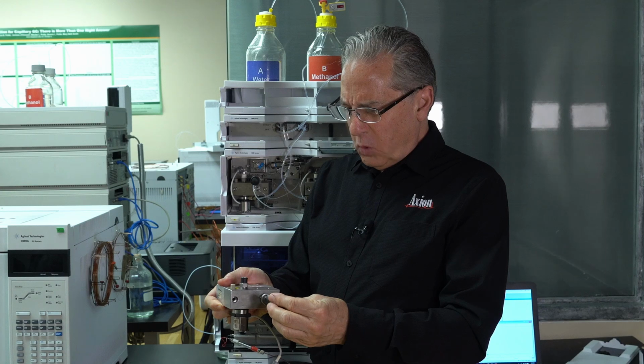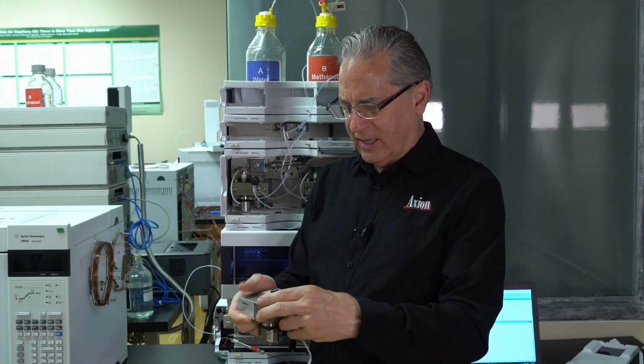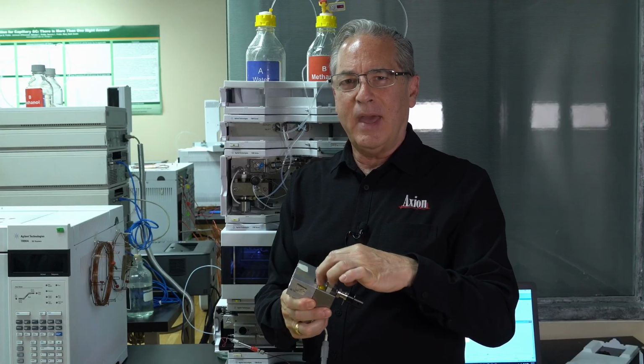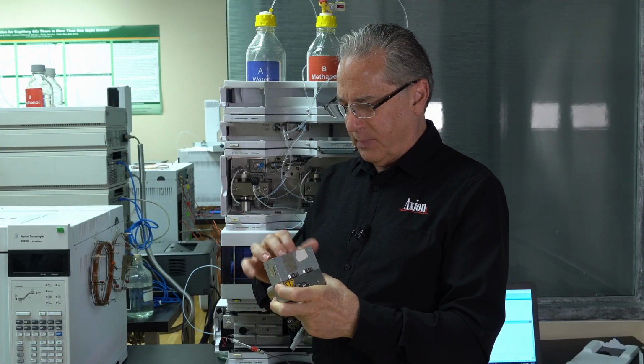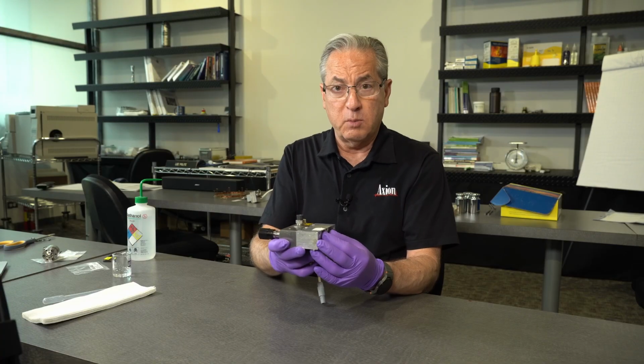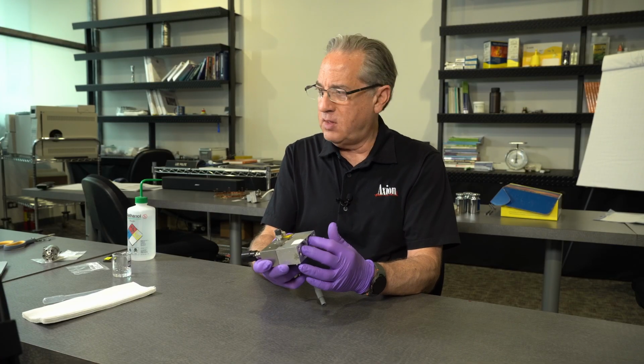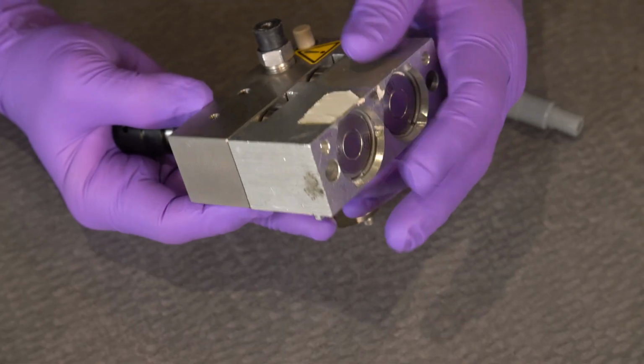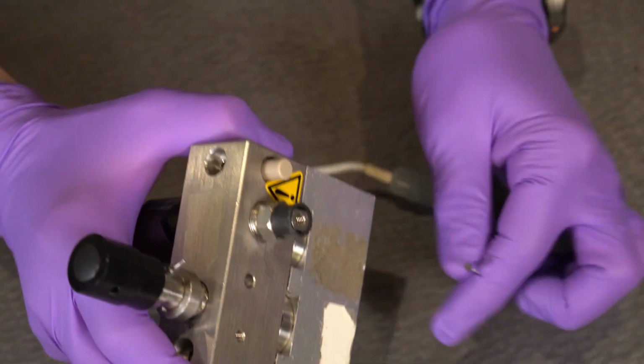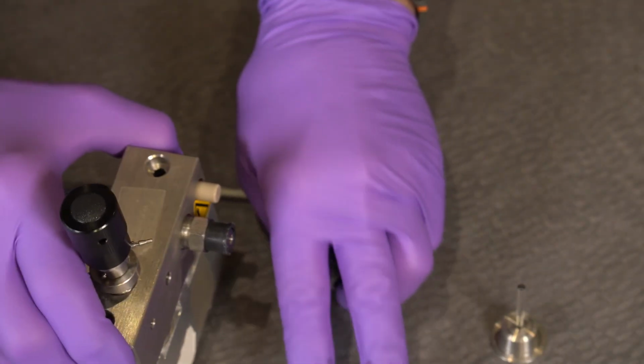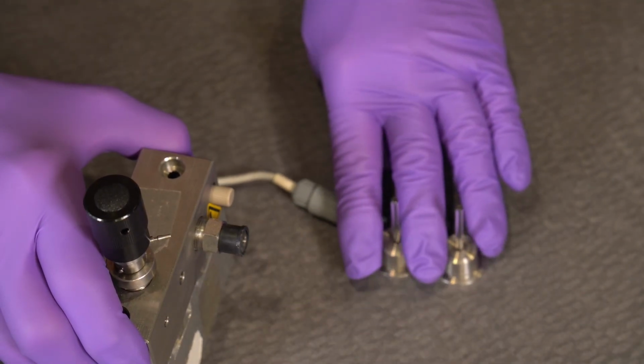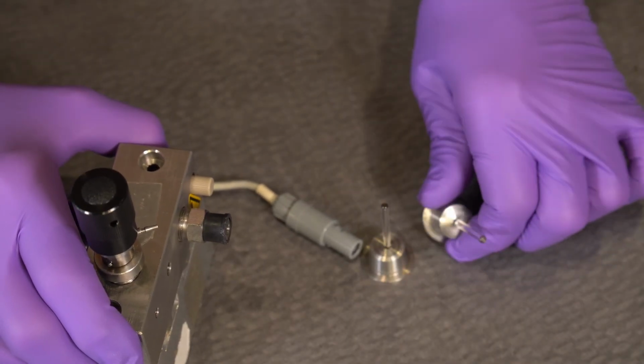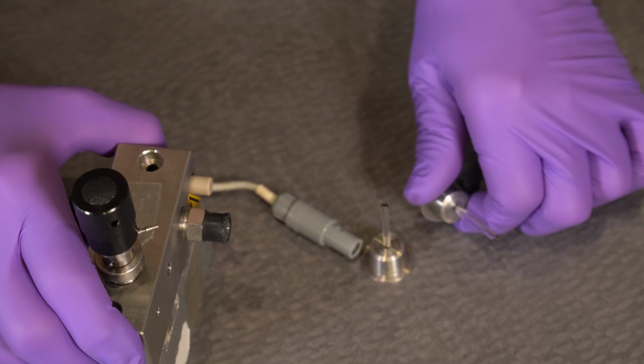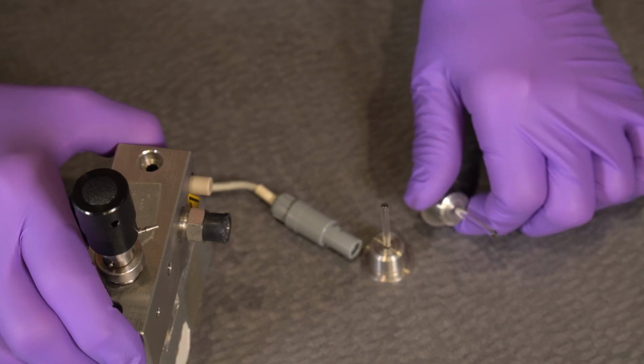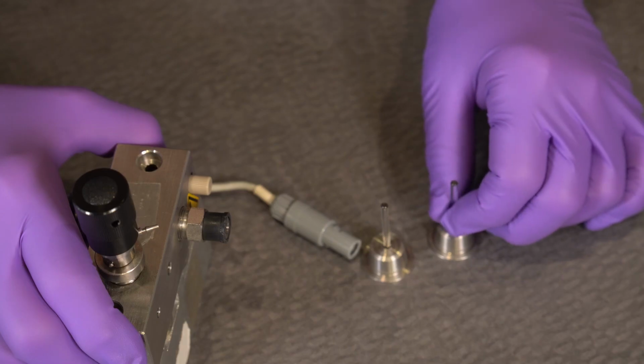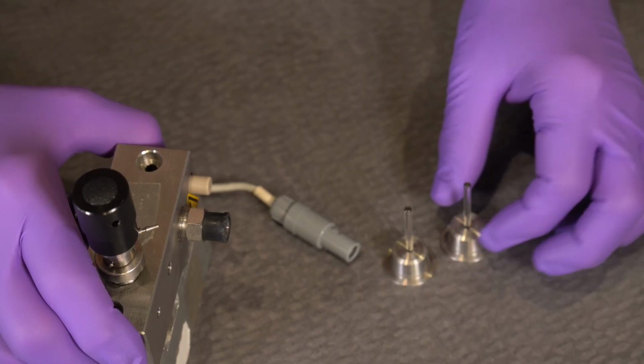So the next thing we want to look at, so that's the PTFE frit itself. The next, the most important thing is going to be inside the pump head, and that is going to be our pump seals. So the first thing, once this has been removed from the LC, I always say you try and remove the pistons first. And the reason is the pistons are made out of sapphire, so they're not really being held in by anything. So if you notice, I just took out these two pieces, and they're sapphire rods. And the reason why we use sapphire is because it's a very hard material, if you remember your hardness scale, and it's also very smooth. So this has to withstand very high pressures. We have to have a seal around it to withstand the pressures.